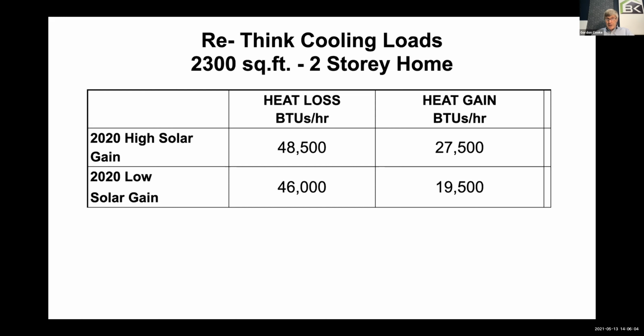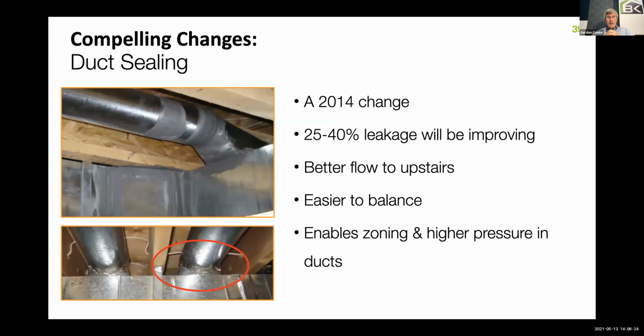And the problem is, again, the 2.5 tons. Even if, well, I don't mind putting in 2.5 tons, that's fine. But remember, that's not the heat gain in the middle of the night. That's the heat gain when the sun is shining on all windows at the same time, which of course never happens. But that's the size you need to put in based on CSA standards. So think about those requirements. So that's a risk, if you will.